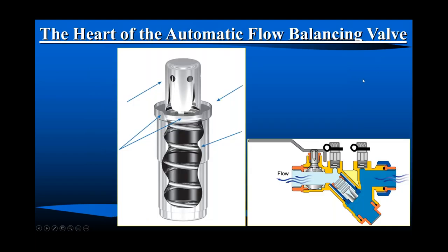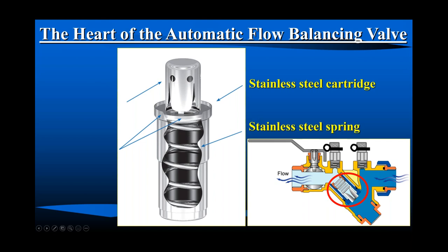So let's talk about what's on the inside of this thing. What makes it different than a manual balance valve that you have to touch the red handle, knob, or disc? So this is our cross-section from before. There's that piston or can or cartridge with its variable orifice. And this is what it looks like. Most of them are stainless steel. There's a number of manufacturers. Some are stamped stainless steel. Some are machined stainless steel. But there's our spring that is also stainless steel. It has to last a good long time in that water. So different grades of stainless steel.